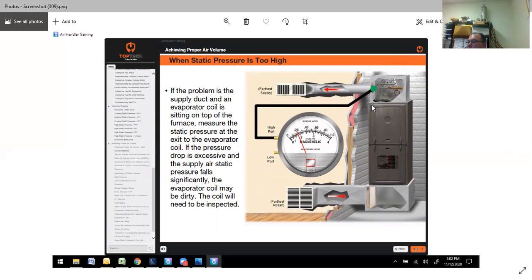Now those are also published in the spec books, so it will tell you exactly what it is, if it's a dry coil or a wet coil. That also will tell you if it's dirty. If you do a pressure drop across that, it'll tell you what your drop is and if it's dirty, and that's a real possibility.